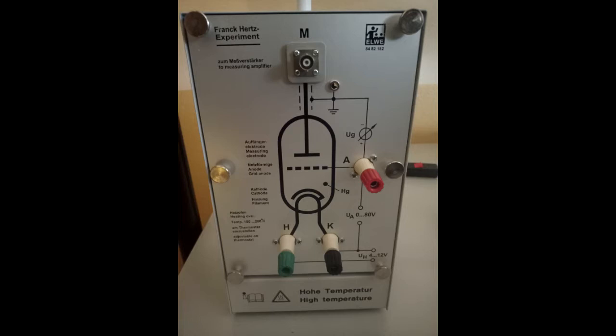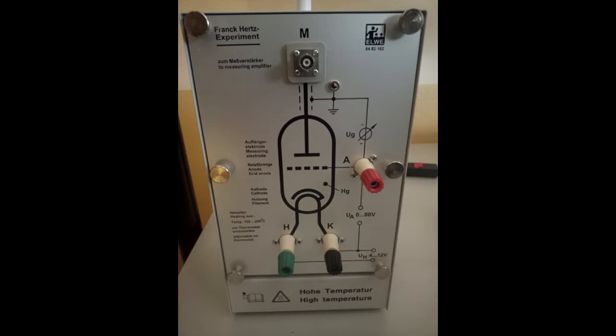This device also incorporates a commutator, which enables the possibility of introducing a variable potential or a constant potential. The intensity exiting just after the collector is very weak, so it's needed a BNC wire to mitigate external noises.